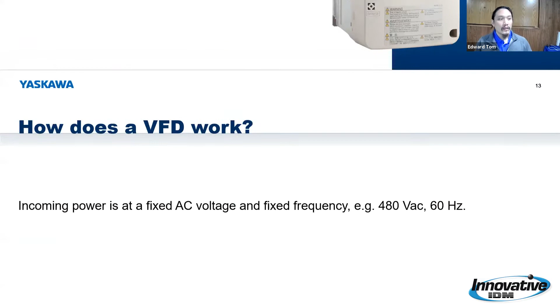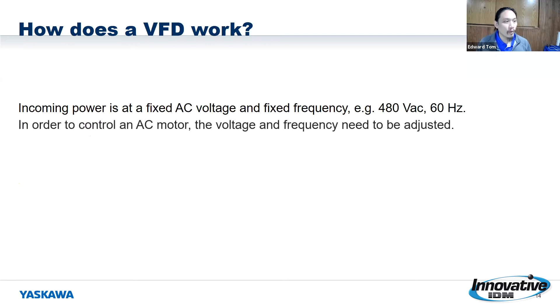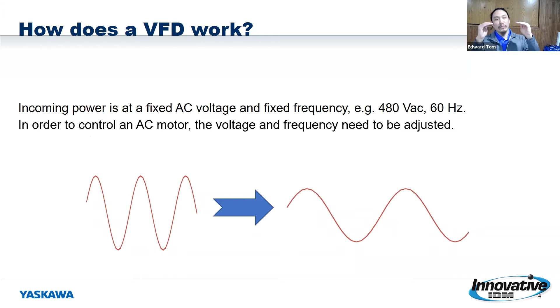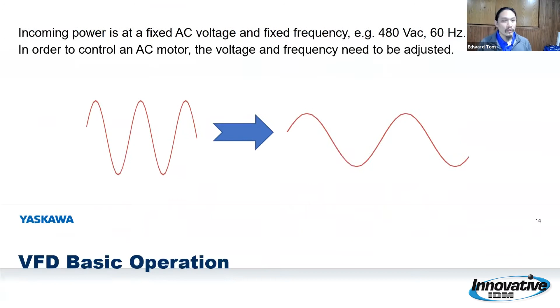Now, I'm going to be talking about all this different magic that it's going to do. At least for some, they may find, hey, this is great. It does all these things, but how does it actually work? What does a VFD actually do to make all of this happen? And right now, your power company is supplying you a fixed voltage and a fixed frequency. And there's not much we can really do about that when it comes to taking that voltage and trying to control the speed of your motor at that point. We talked about the mechanical methods, but that certainly has its drawbacks. But what we found is that in order to control an AC motor, to vary the speed of that motor, if you adjust the voltage and the frequency to it, you can actually change the speed of the motor, going from a faster speed to half of it or even lower, and hence giving you that control of the motor itself.